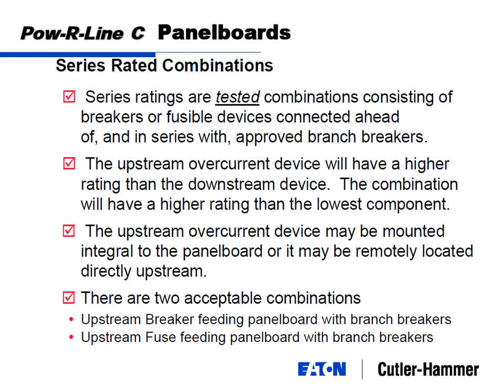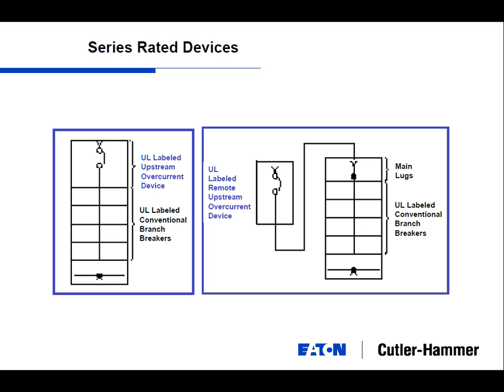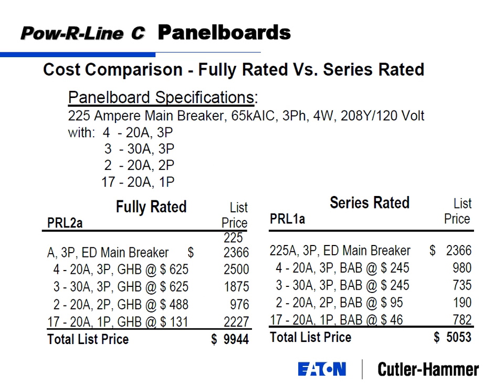The upstream device may be mounted inside the panel board as a main breaker, or you could actually have a main lug only panel and series rate with the upstream switchboard feeder breaker feeding that panel. That is acceptable. So, you know, this is the way most people will do it, but this is also very good. And if you talk about cost-effective ways, you don't even have a main breaker here, and you're series rated, you're taking full advantage of cost savings. And I think this is the one, yep.